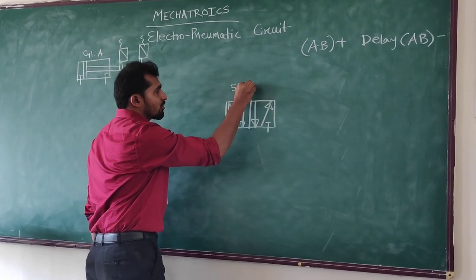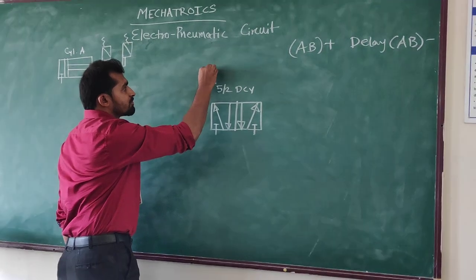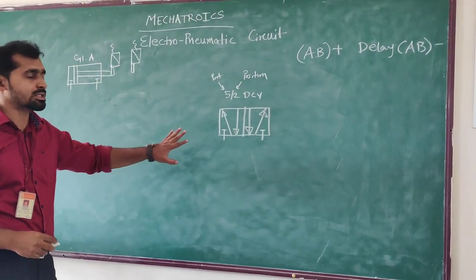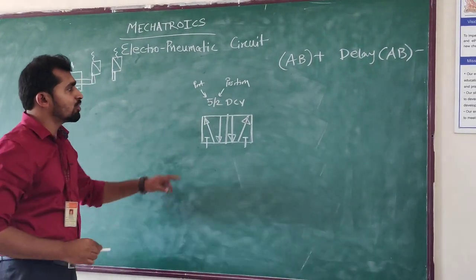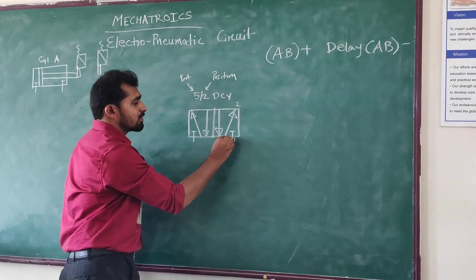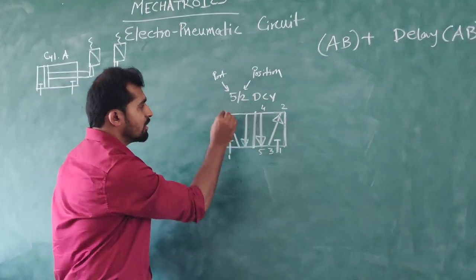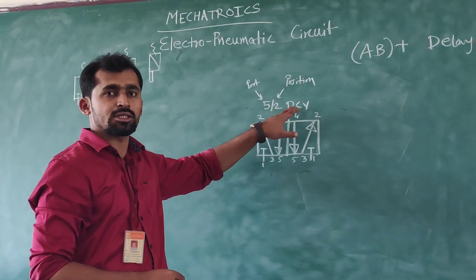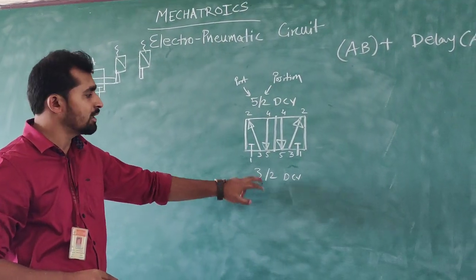The 5x2 directional control valve is also called a DCV. In 5x2, the 5 refers to ports and 2 refers to positions. So there are 5 ports and 2 positions. The first position and second position each contain 5 ports numbered 1, 2, 3, 4, and 5. That is why this valve is called a 5x2 directional control valve. If the question asks for a 3x2 DCV, then you draw the ISO symbol of a 3x2 directional control valve — 3 ports and 2 positions. For a double acting cylinder we use a 5x2 directional control valve.